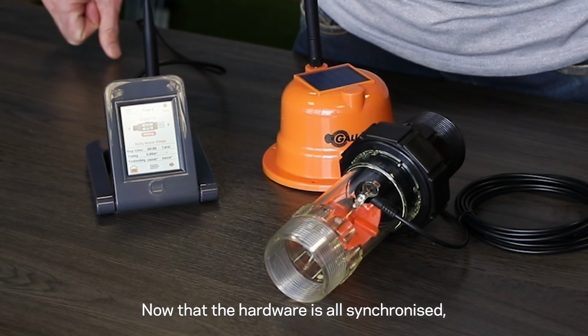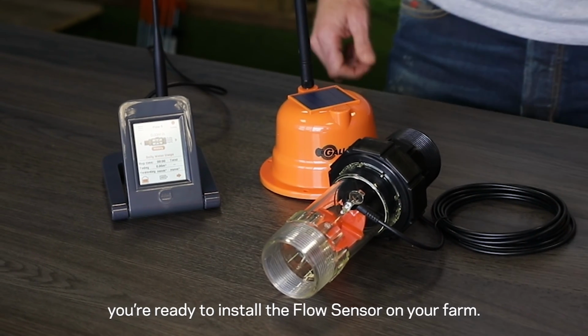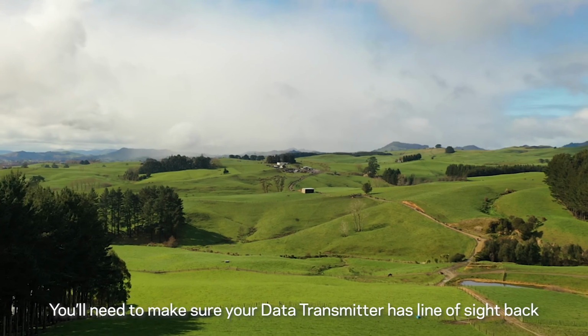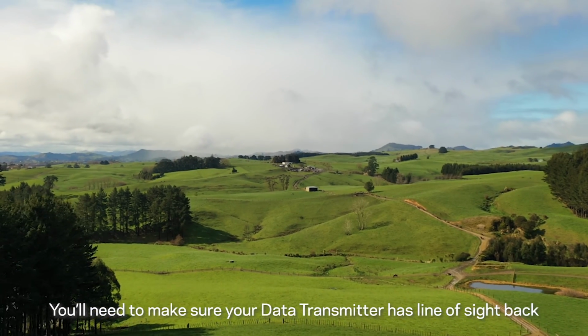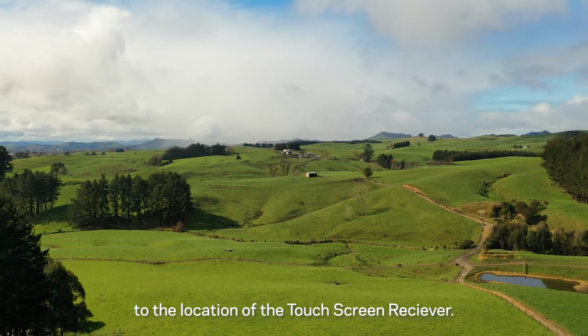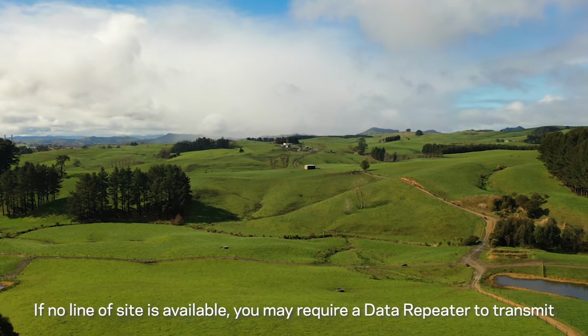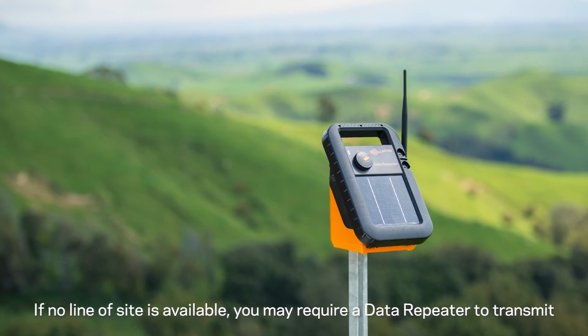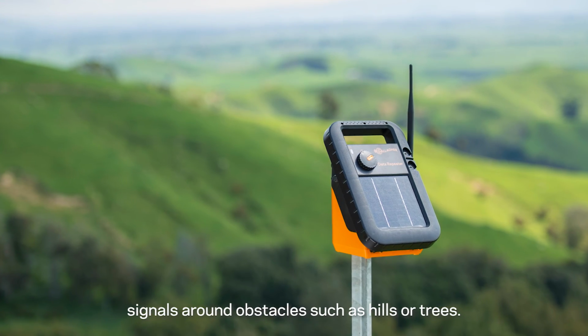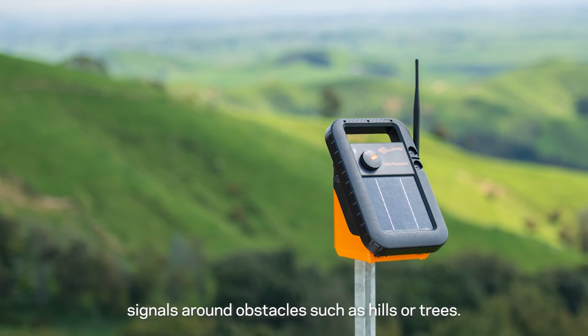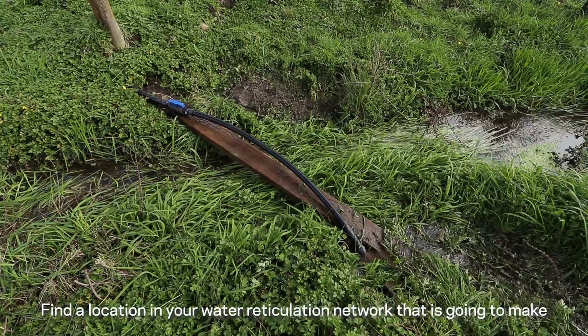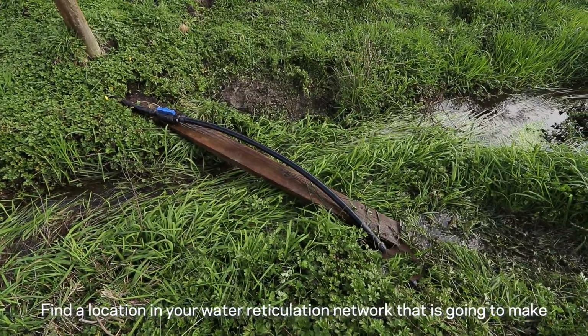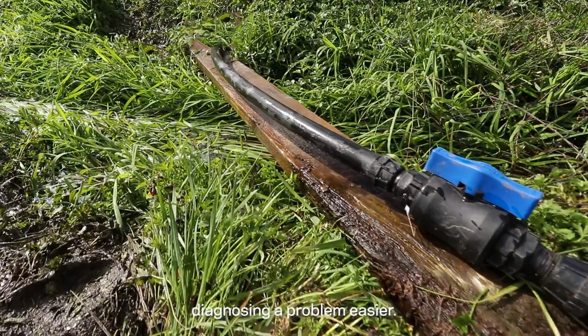Now that the hardware is all synchronized, you're ready to install the flow sensor on your farm. You'll need to make sure your data transmitter has line of sight back to the location of the touchscreen receiver. If no line of sight is available, you may require a data repeater to transmit signals around obstacles such as hills or trees. Find a location in your water reticulation network that is going to make diagnosing a problem easier.